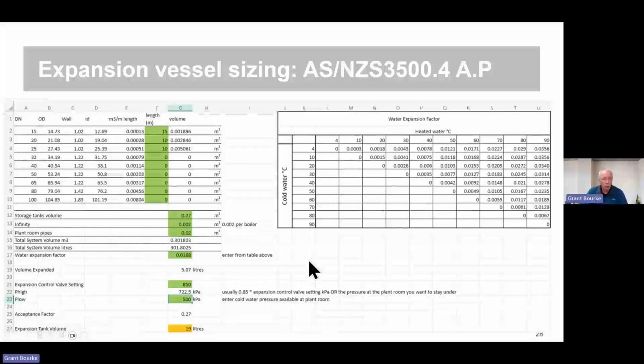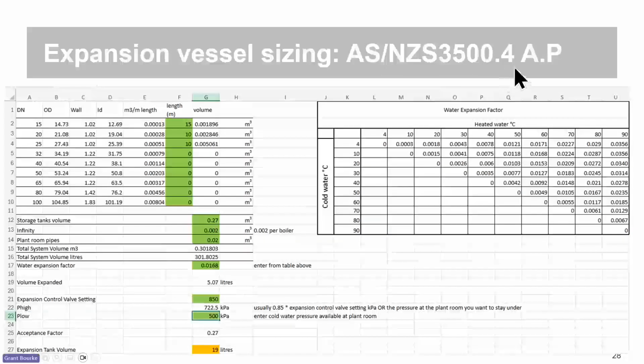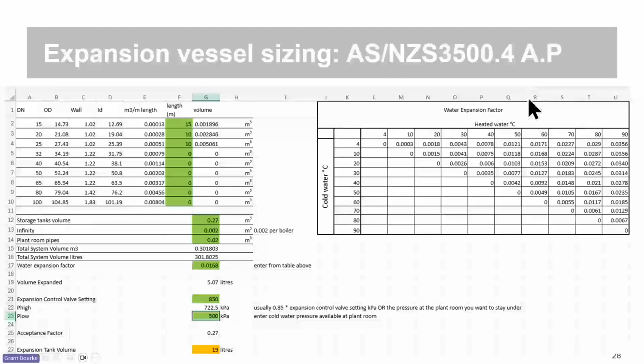Pressure vessel sizing. There's an appendix way down the back of 3500.4 that you might have never come across, Appendix P, that's got a method for doing that. We're running out of time a little bit, so I'm not going to go into detail, but again, we've got a spreadsheet. It's on the second page of the spreadsheet for the pipe sizing, and we'll make that available to you after the webinar. You can use it if you want.